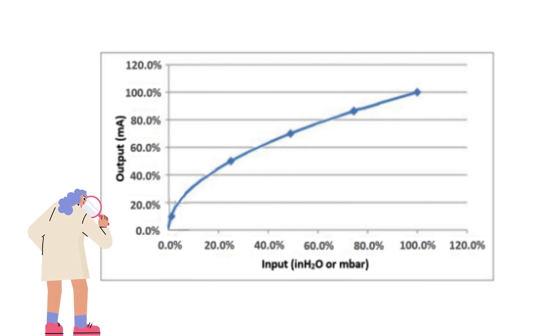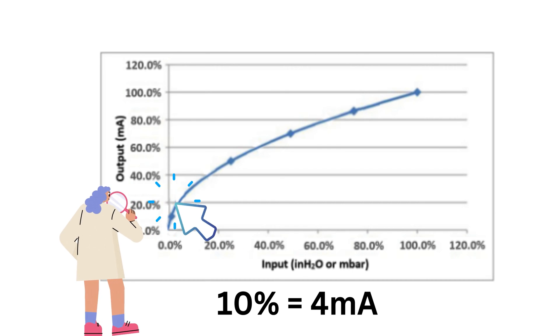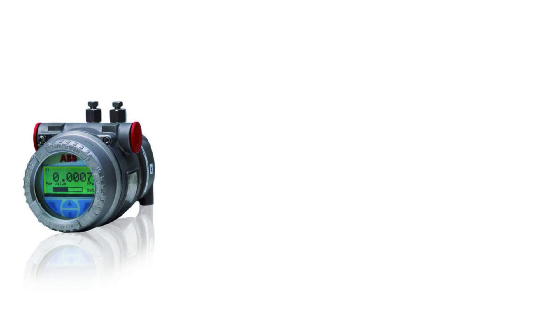Therefore, vendors will define a low flow cutoff for the flow meter. That means that the output signal will be set to 4 mA once the flow drops below 10%. The low flow cutoff is only present in DP transmitters with internal square root extraction.